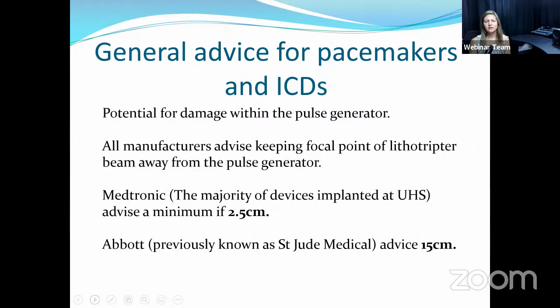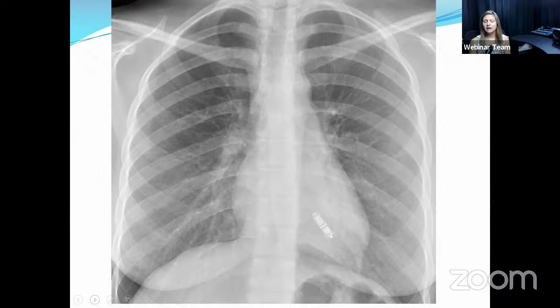So some pacemakers, like Medtronic, advise a minimum distance of 2.5 centimeters, some others 15 centimeters. So we need to be very careful which type of pacemaker our patient has. And in most hospitals, there is a team that can help in supporting this. This is an example of a pacemaker that, in this case, would probably be less than 15 centimeters from a possible kidney stone. Our lithotripsy, as we said, is an electromagnetic source, and therefore there could be some interference, and the pacemaker can misinterpret that.